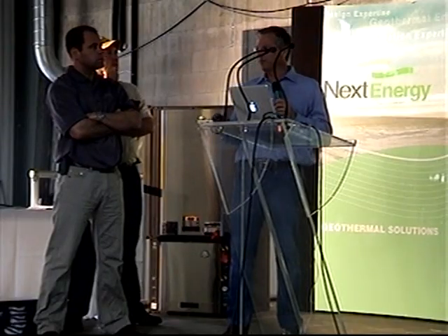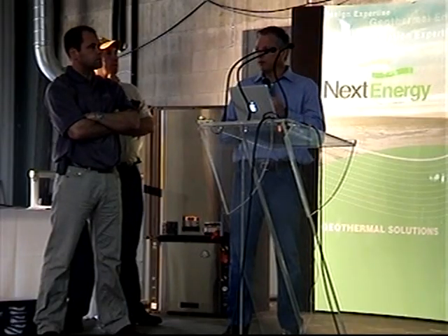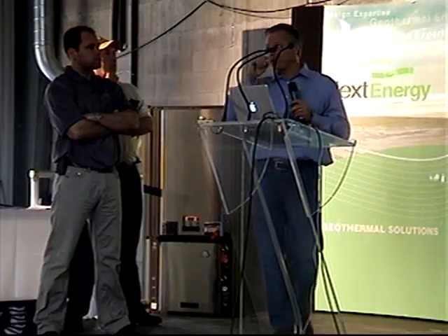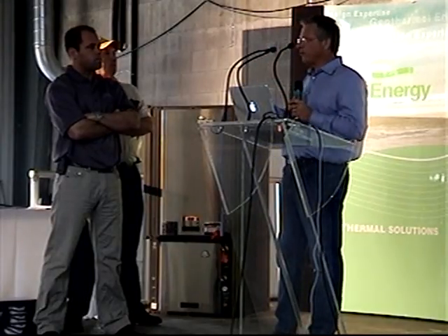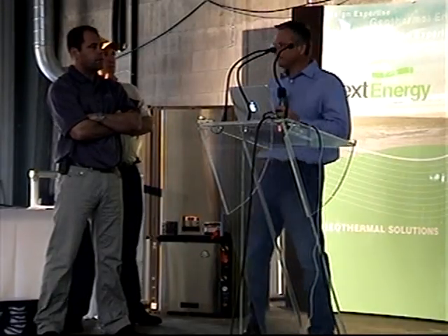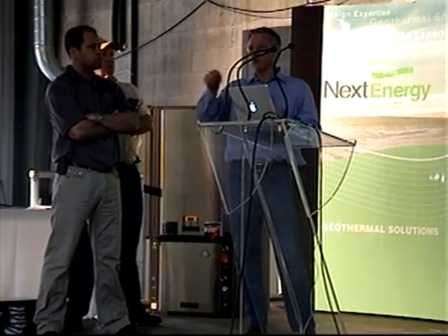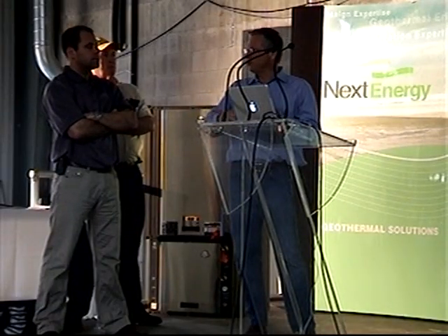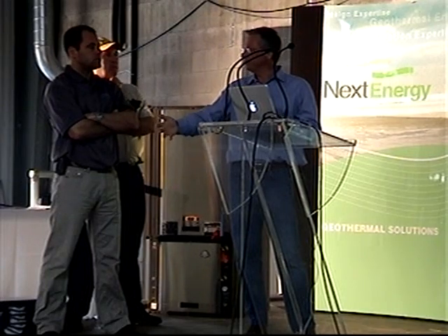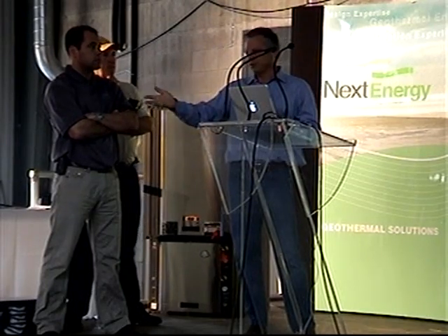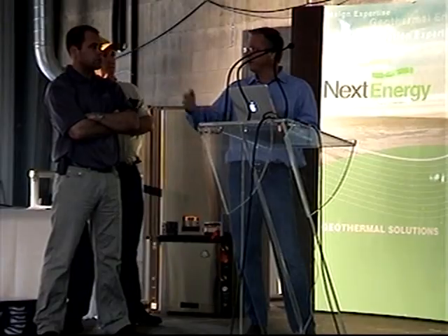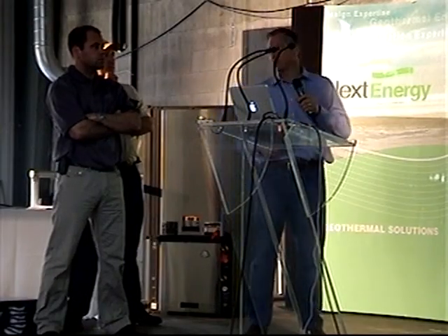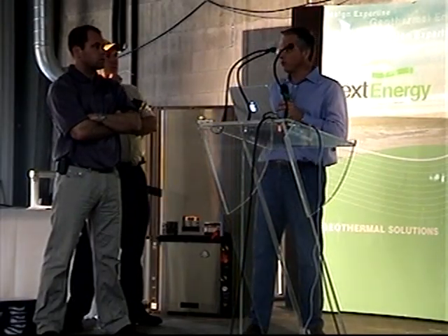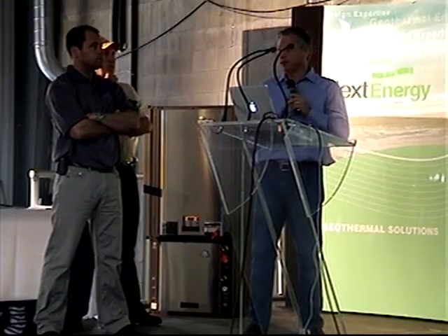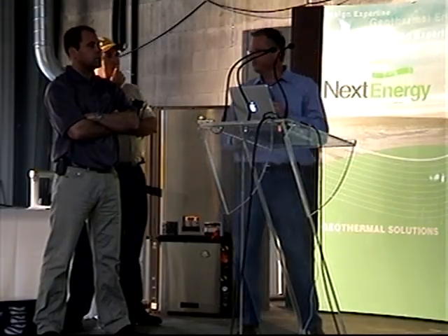Basically, it looks at the voltage coming out of the transformer and does it that way. Do you guys have 240 volts? Is that what you typically have? If you would ever accidentally have the transformer on the 208 volt tap, then you'll have real high low voltage coming out. It'll make it jump up. Instead of 26 volts or whatever, you might have 30. I think it's around 30 volts where that thing would start tripping. So, if you do have an overvoltage, first thing you might check is to make sure your transformer's on the right tap.